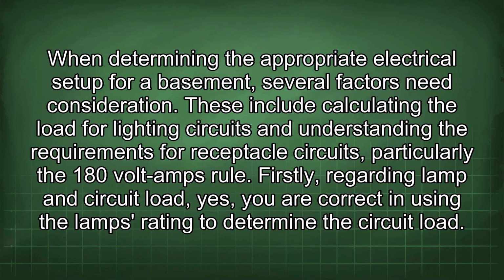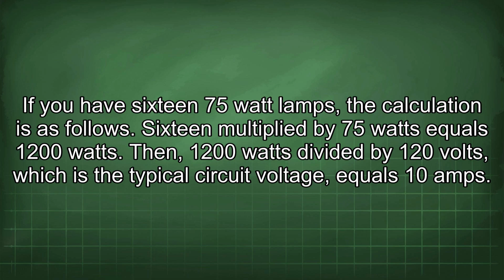When determining the appropriate electrical setup for a basement, several factors need consideration. These include calculating the load for lighting circuits and understanding the requirements for receptacle circuits, particularly the 180 volt amps rule. Firstly, regarding lamp and circuit load, yes, you are correct in using the lamp's rating to determine the circuit load. If you have 16 75 watt lamps, the calculation is as follows.